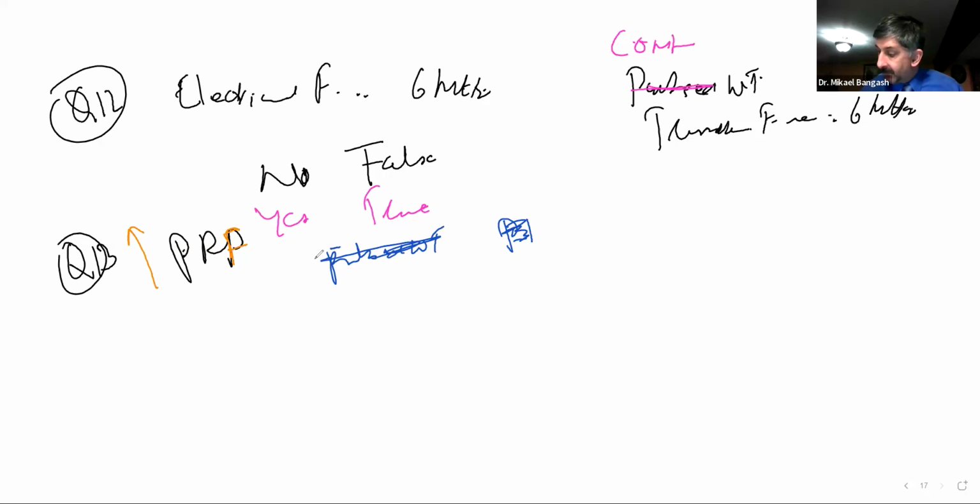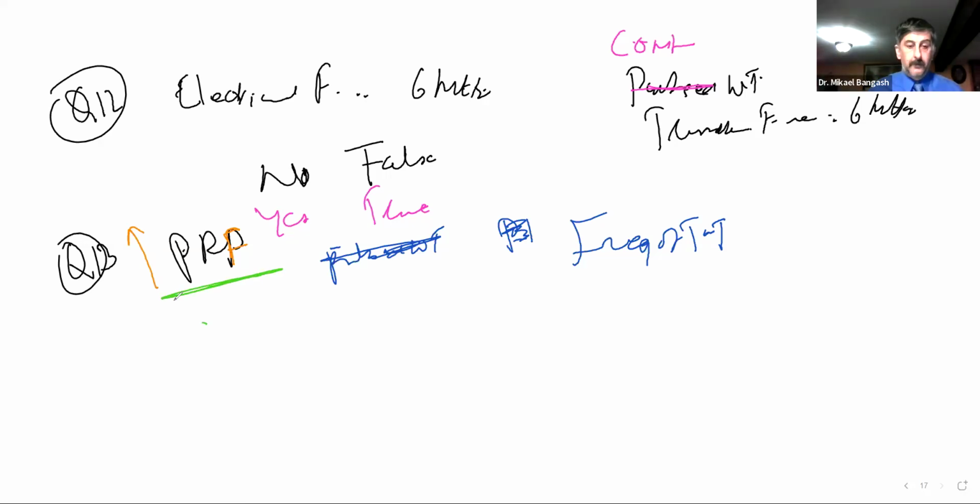then the frequency of the transducer, is that frequency going to be the same? Yes. And why is that? Mainly because pulse repetition frequency and the frequency of the transducer are not related.